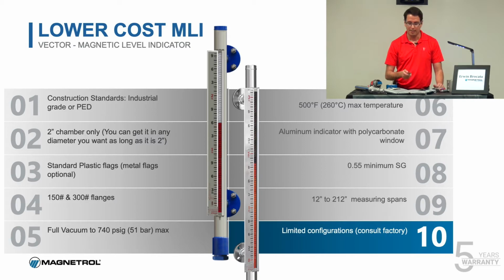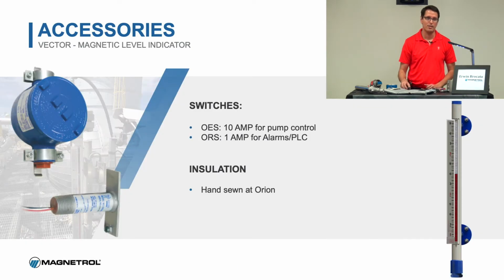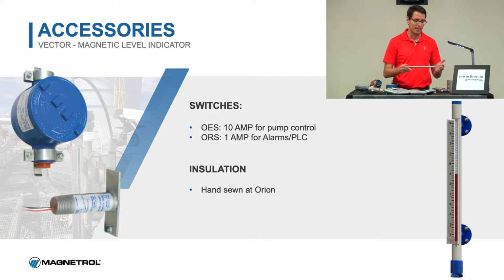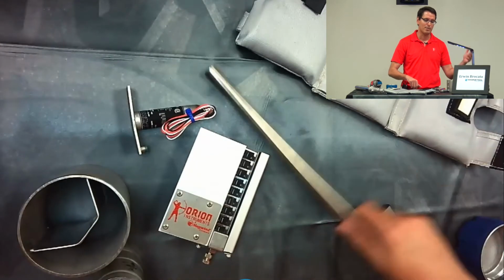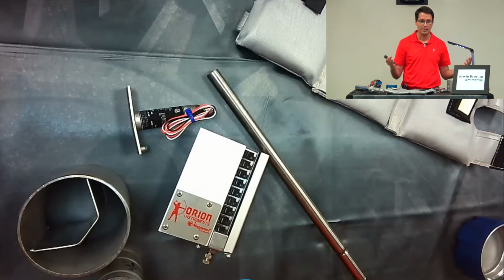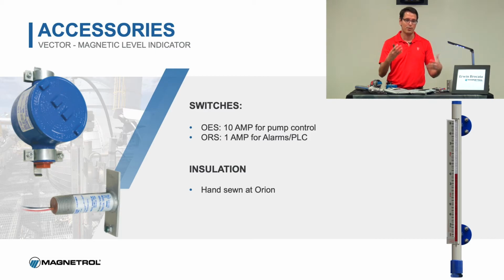Okay, good. And you can also do transmitters on these devices. That is obviously a little bit more expensive. This is just the probe of a Jupiter transmitter that you can see here. Can you see it on the other one? Okay, good. This is the probe, but it's connected to a transmitter. That transmitter is a 4 to 20 device. It's a little bit more expensive, but if you need a control on the device besides just the local indicator, you can do it with switches or with a transmitter connected to a PLC. We can also provide you with a controller, or we wouldn't because we don't make controllers, but our local representatives carry controller lines, and they can hook it up to the device so they can power it, and it can give you a local indicator as well.